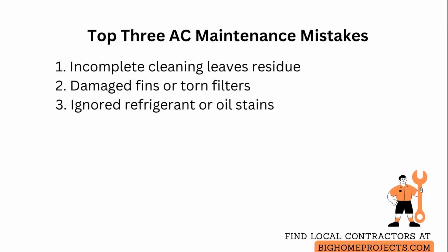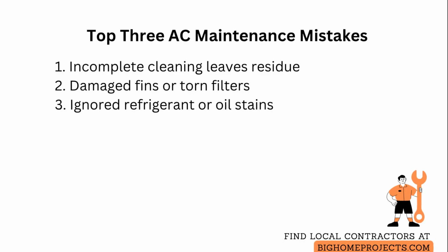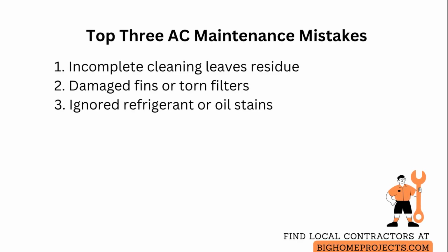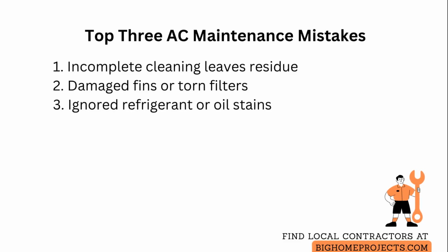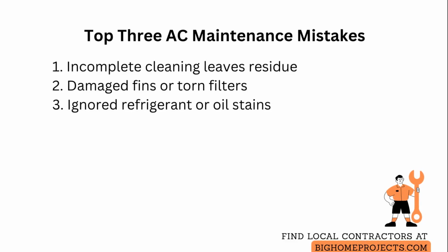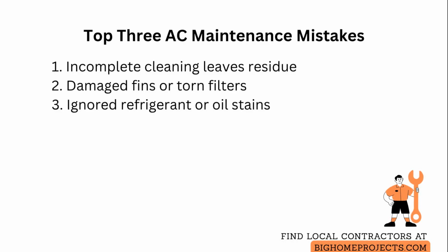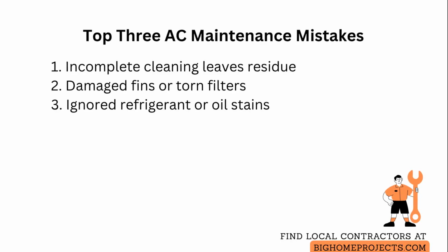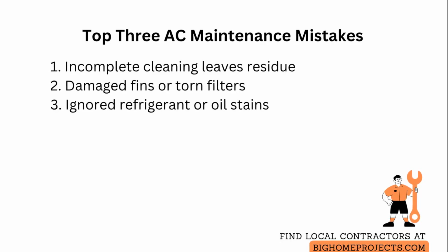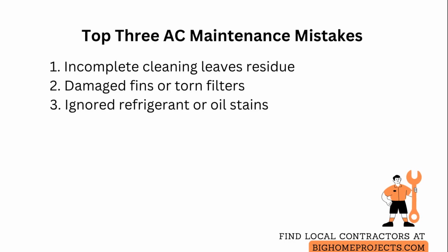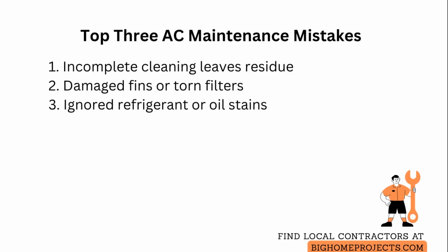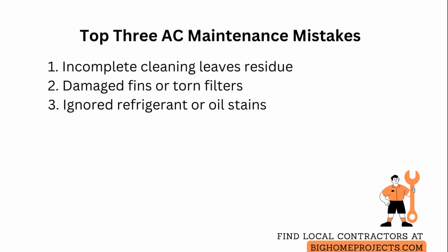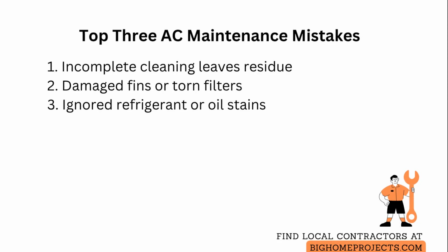Three common issues are incomplete cleaning that leaves residue and reduces benefit, which you avoid by following product dwell times and rinsing from the opposite side of airflow. Damaged fins or filters that cut airflow, fixed by replacing torn filters and using a fin comb to straighten fins rather than forcing them. And ignoring refrigerant or oil stains because those signal leaks, in which case you stop the unit and call a licensed technician rather than attempting refrigerant repairs yourself.